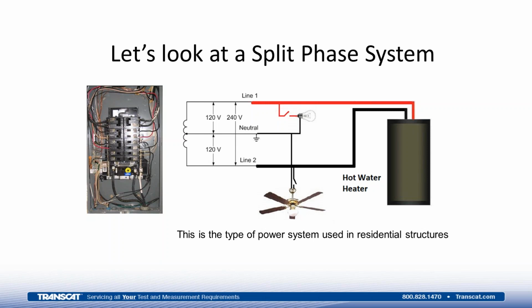You can actually have a 240 volt load running off of two conductors and no neutral present. Now, to monitor the three items that are on this screen, I would connect voltage leads up to L1 and L2 and connect the third lead up to the neutral. I would then put two CTs, one around L1 and one around L2, and that would allow me to measure all three loads being run off this transformer.